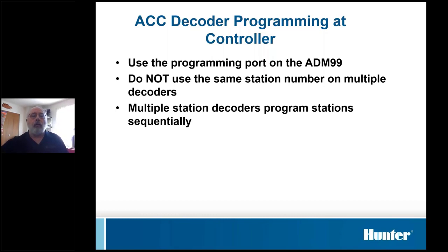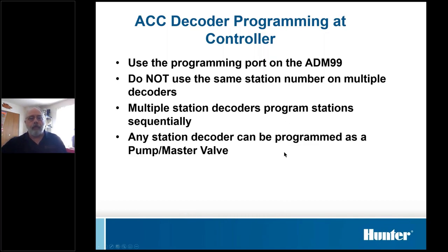And when you're programming from the controller, it programs the stations sequentially. In other words, say you put station 7 in for the first station on a 4 station decoder, it's going to make the second output 8, the third 9, the fourth 10. When you're programming at the ACC controller, it's sequentially.